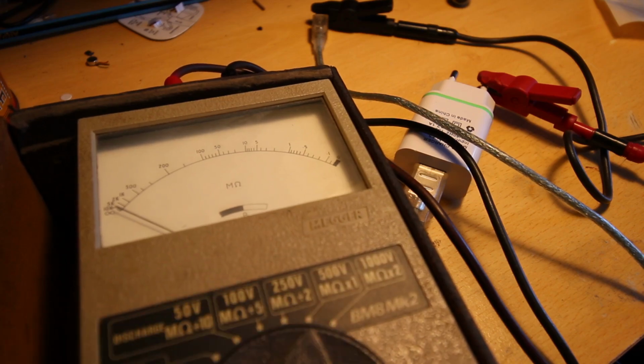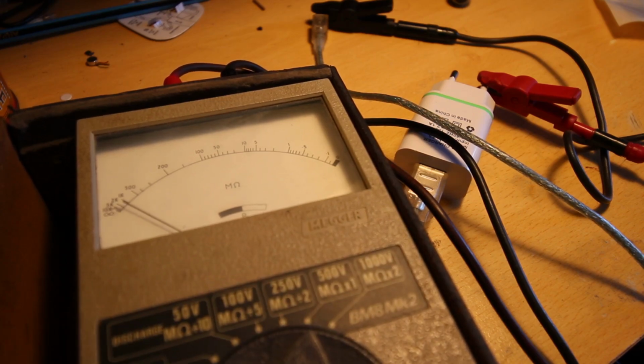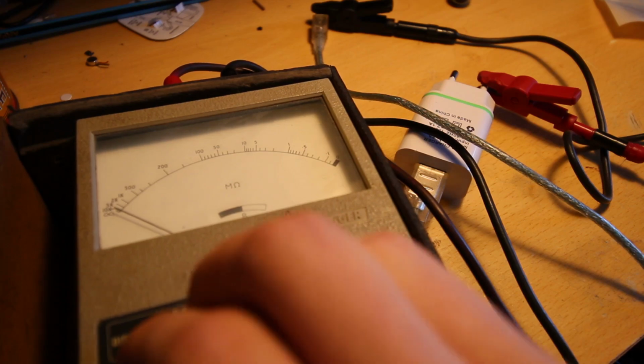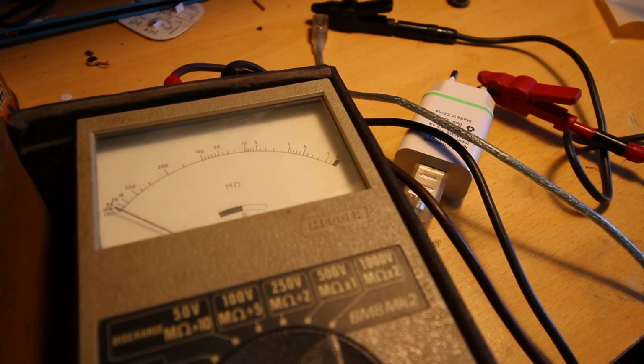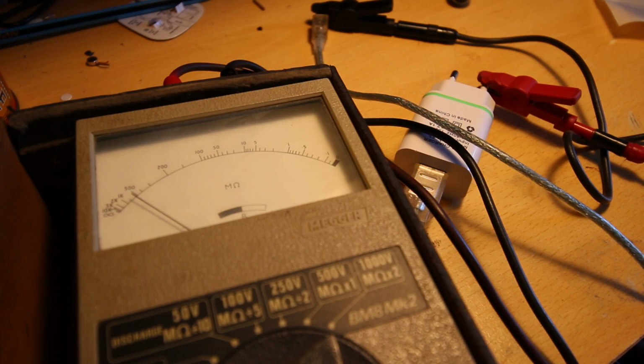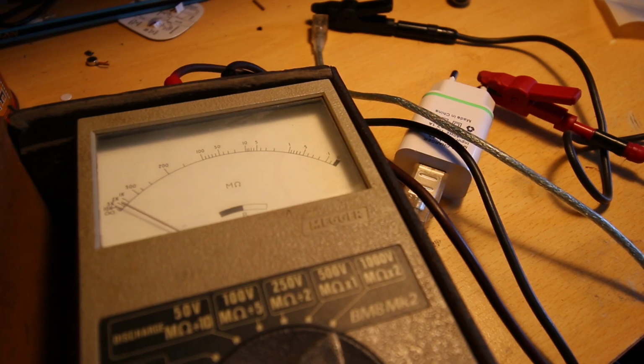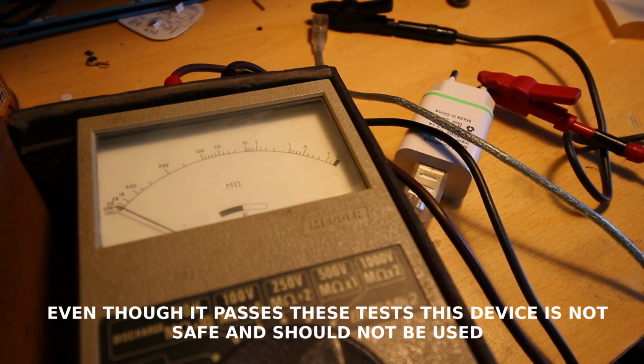And nothing. Set it to 500 volts. Just about in between 2000 and 5000 megohms. Then we'll set it up all the way to 1000 volts, and that's just under 2000 megohms. So again, it's passed all of those perfectly fine.